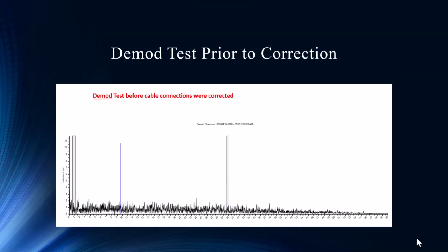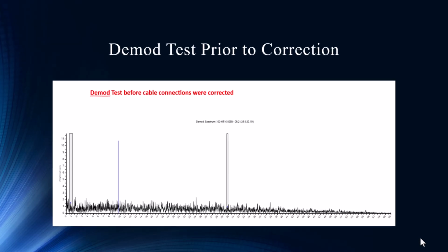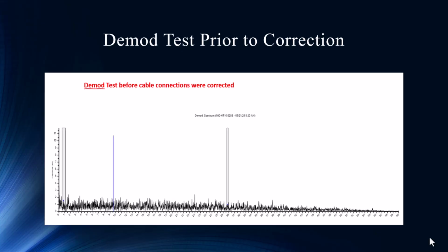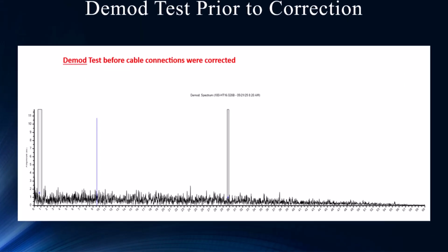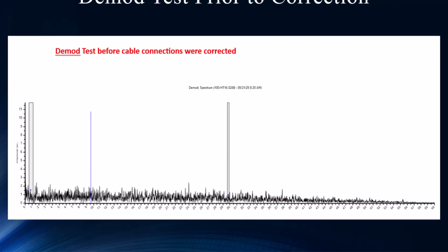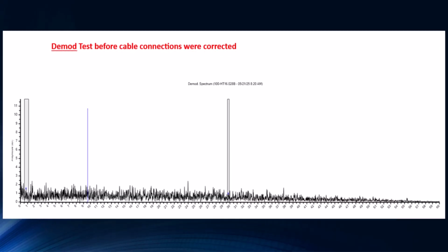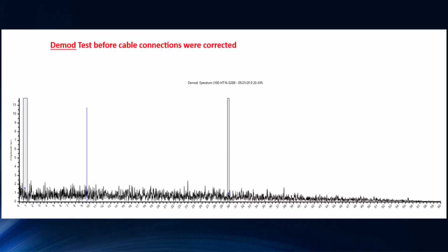And when we come over here, this is probably the most telling, because there's a significant amount of noise in the circuit. Yeah, it makes it very difficult, specifically for machine train analysis. You've seen some of the case studies in the past where we used this exact test to identify gear issues on the cooling fans. And it's hard to do it now.